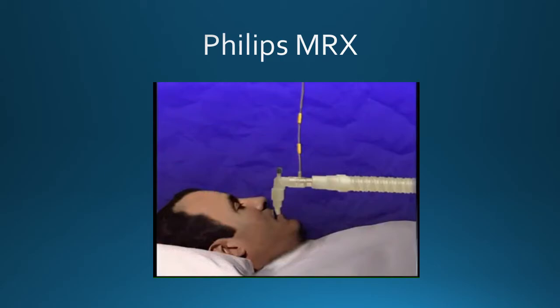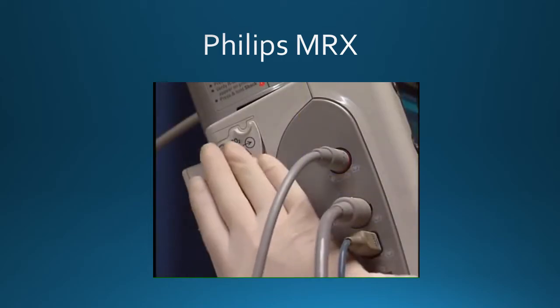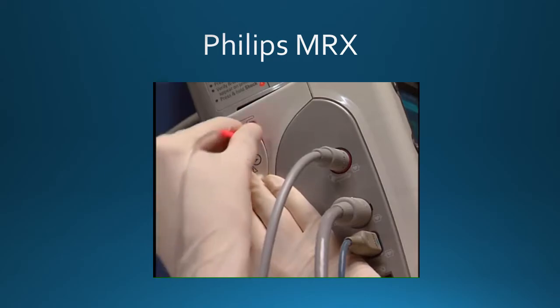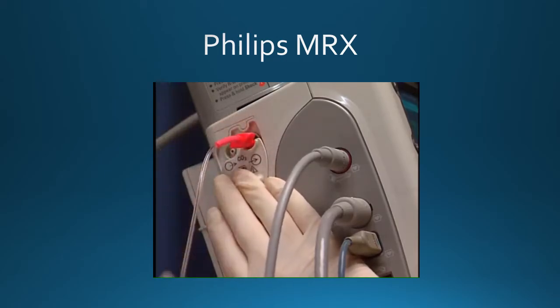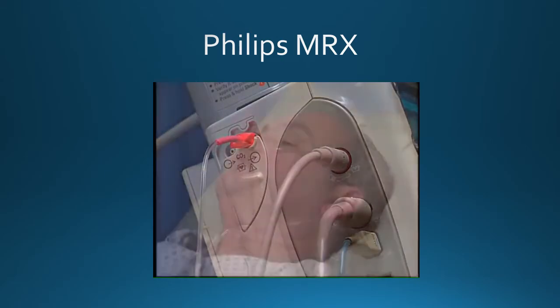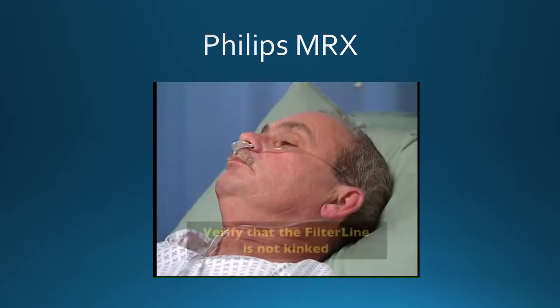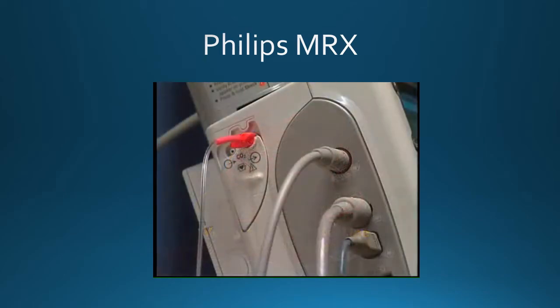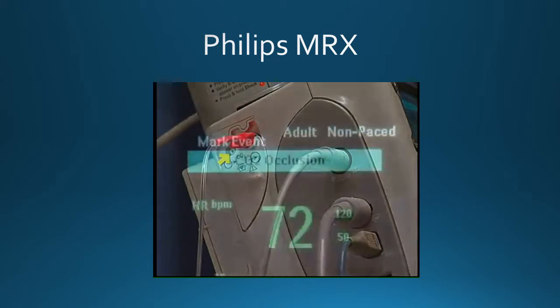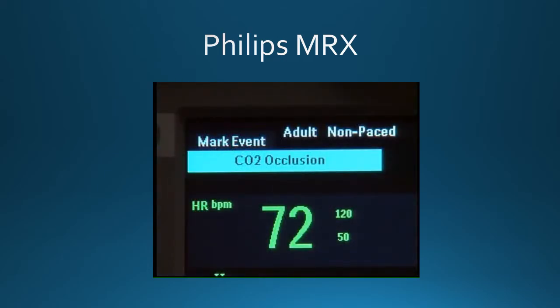When using a filter line set, place the pre-attached airway adapter on the ET tube. Attach the female luer connector of the nasal cannula or airway adapter to the CO2 inlet connector on the measurement connector module. Regardless of type, nasal or intubated, verify that the filter line is not kinked. To remove exhaust gases from the system, connect an exhaust tube or closed-loop kit to the connector. Evaluate the filter line if a CO2 occlusion inop appears or if the readings become extremely erratic.